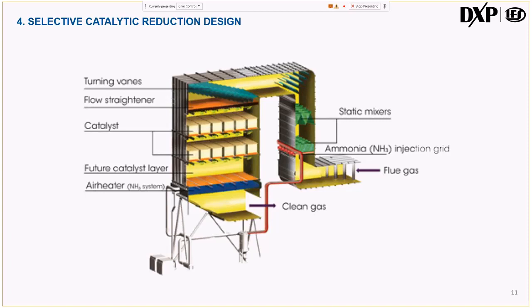You're going from a stable state to an unstable state, and therefore you have to have some higher temperatures for the reaction to take place. And that's why you have a separate duct burner in the HRSG for this SCR reaction. If it gets too cold, then you've got to heat the HRSG up so that you get the temperature for the SCR catalyst reaction to take place.